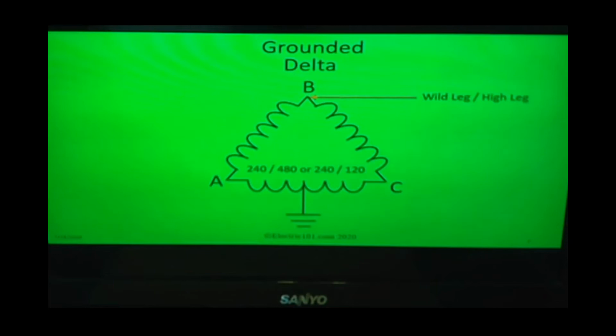Primary versus secondary. Now, one of the transformers you've got to watch out for is what's called a grounded delta system. These were installed a long time ago, in older areas, older buildings, with older equipment, and you'll have what's called a wild leg or a high leg. The voltage on this transformer could be one of two voltages. You might have three-phase 480. So measuring between A and B, you get 480. Measuring between B and C, you get 480. And measuring between A and C, you get 480.